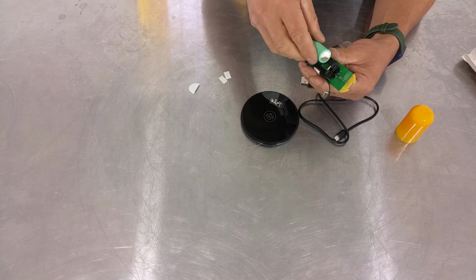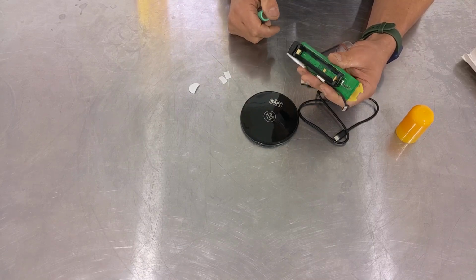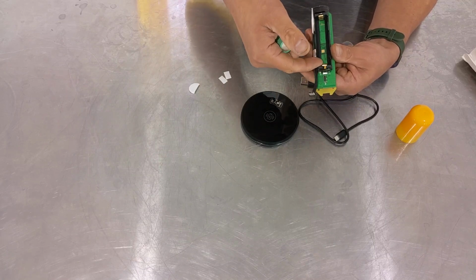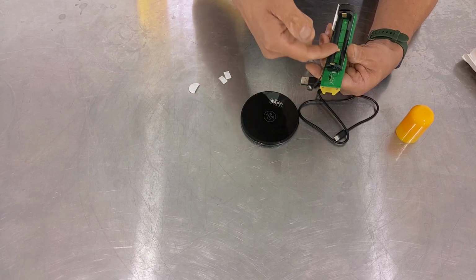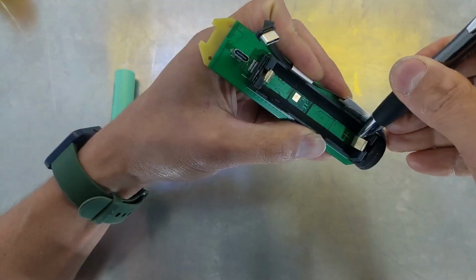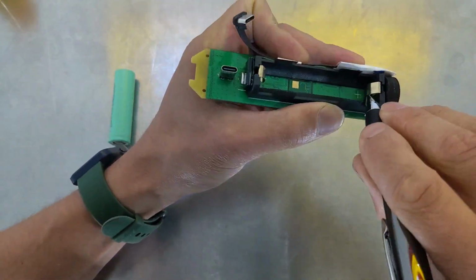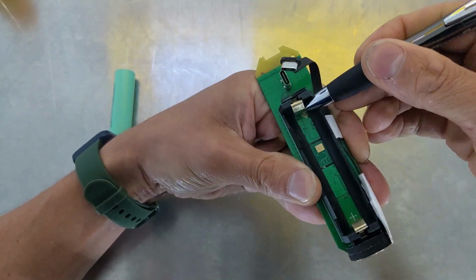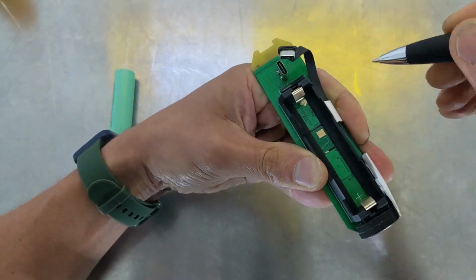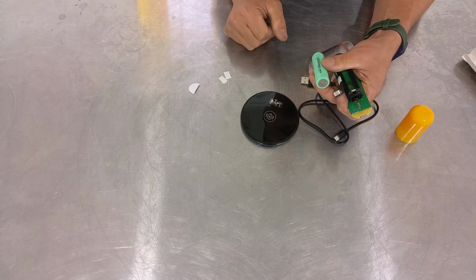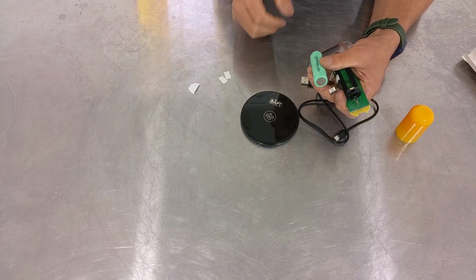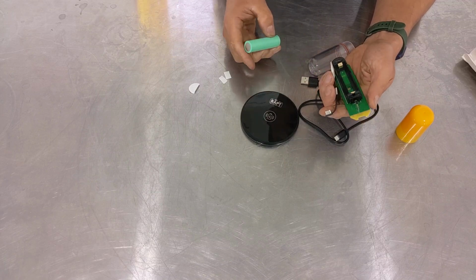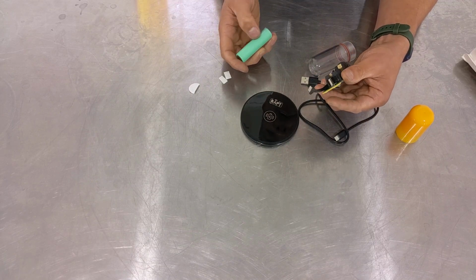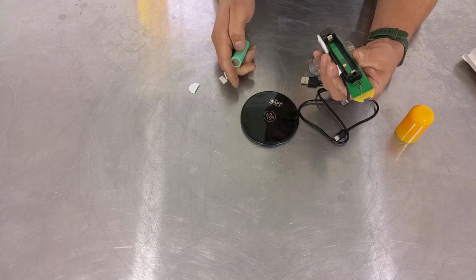If it doesn't feel like the terminals are touching hard enough, what you can do is just get a screwdriver and bend this terminal out a little bit as well. So just bend it out so it's pushed closer to the battery, and that'll make a really, really good solid connection. So if you find you've got a pill that just disappears offline or something like that, or the telemetry just stops coming through at some point and doesn't come back, that has been one of the most common issues that we've seen, but really, really easy to fix and troubleshoot that one.